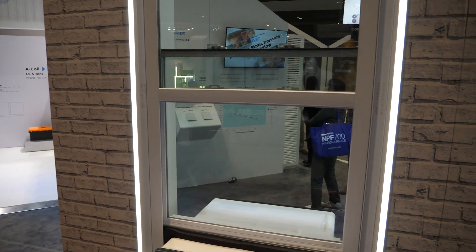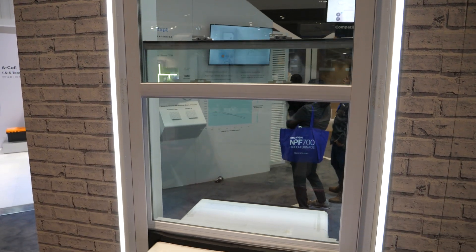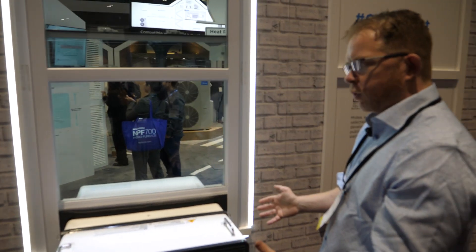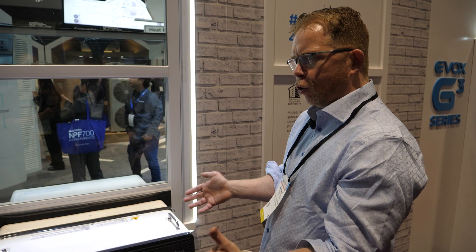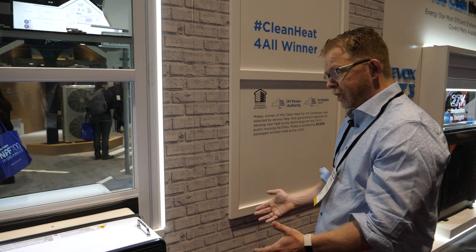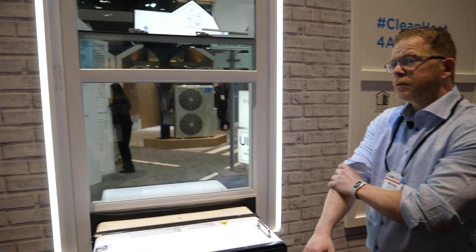This is a really cool unit — about 9,000 BTUs, which is going to cover a lot of the market, especially for room air. It covers a living room or maybe a bedroom. As you look at a lot of apartment units with that central design — kitchen connected to the living room — 9,000 BTUs of heating and cooling is a great leap forward for an old building that just has a boiler. Installation time is probably 30 to 45 minutes. When they installed 36 units, the first day doing just six units working with the maintenance guys, they got those first six done in about three hours.